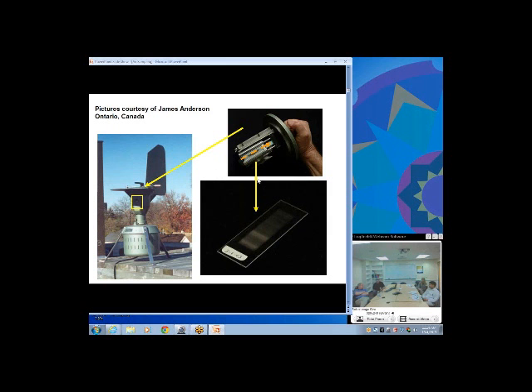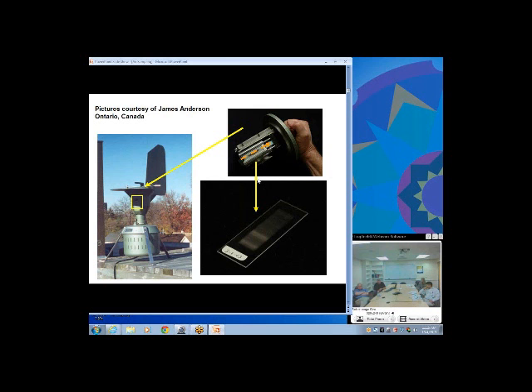The wind effect matters most when the vacuum fan has limited capacity — if it's not operating at excess capacity, the load falls when wind blows toward the unit and sampling speeds up. However, if operating properly, you're pulling a critical vacuum on the inside, and the force on the outside can be no greater than air pressure, about 14 pounds per square inch, so small changes should not affect it.